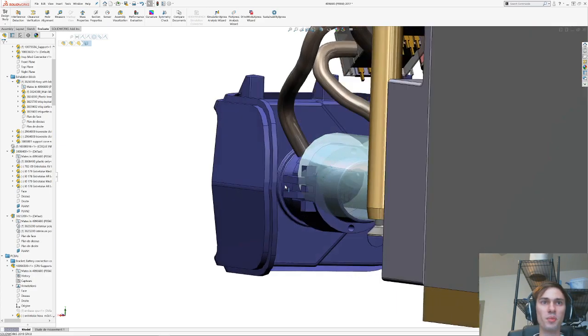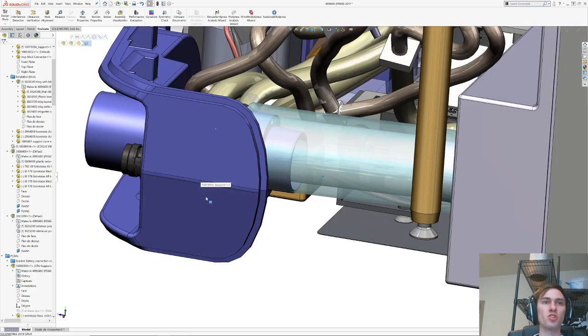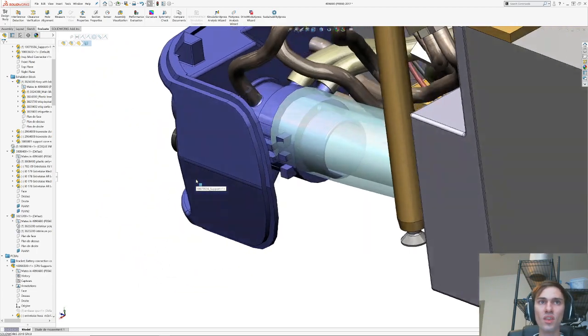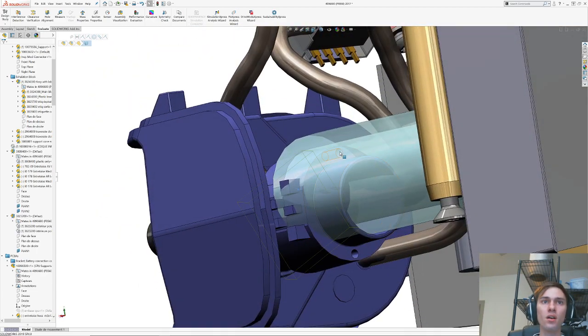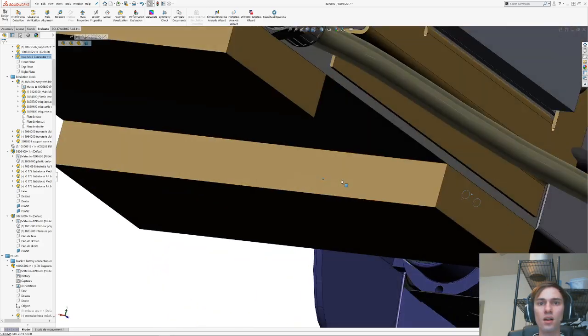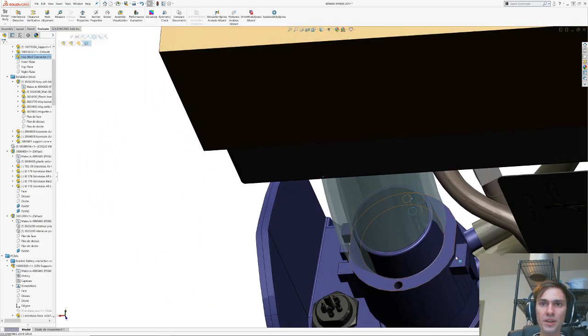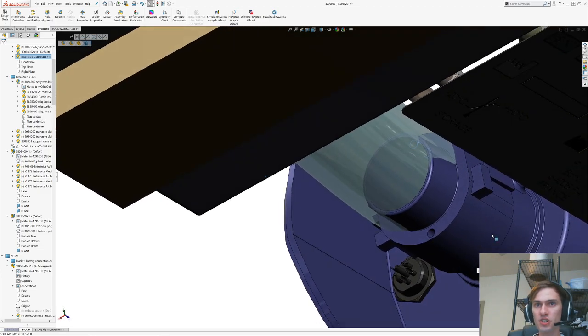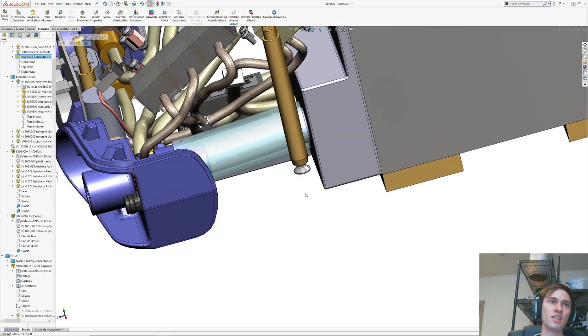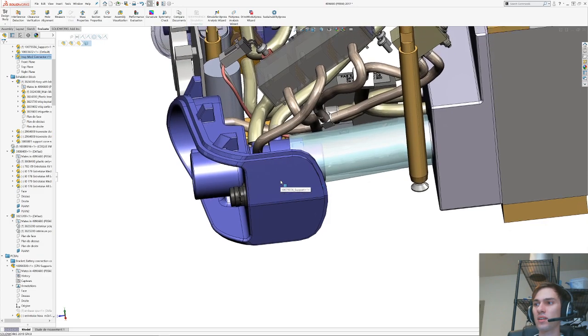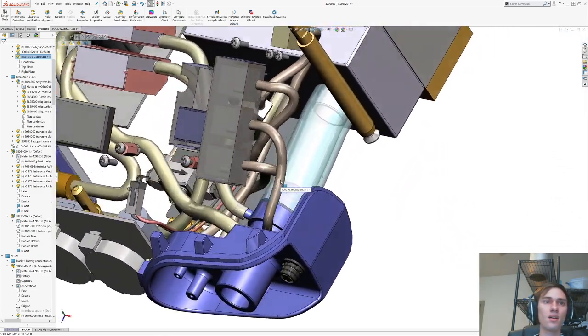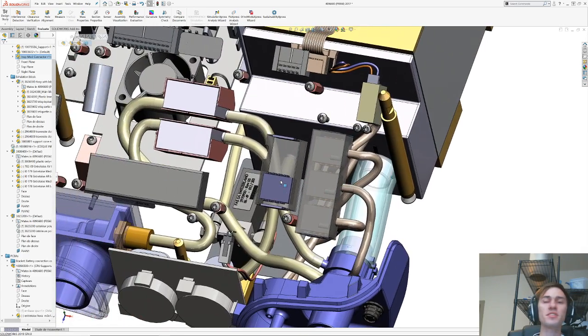Also, that connector isn't wired up to anything. I wonder if that's supposed to... Oh, I bet the wires are a part of the PCB, which I hid. That would make sense. Okay. Weird. So they're measuring the delta P across this screen. Can anybody think why we do that? Maybe the screen causes like a known pressure drop? I do not know. I do not know why it would do that.